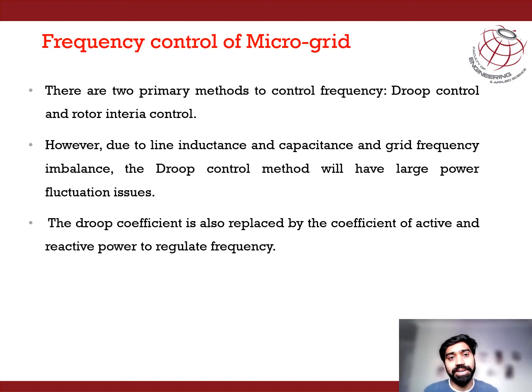Hi, my name is Lay, and I'll be discussing frequency control of the Ramea Island microgrid. There are two primary methods of frequency control. First is the droop control, and second is the rotor inertia control. Due to the high impedance of a line, there are high oscillations of power fluctuation when we control frequency. So the droop control method will emphasize controlling frequency as well as the power oscillation.